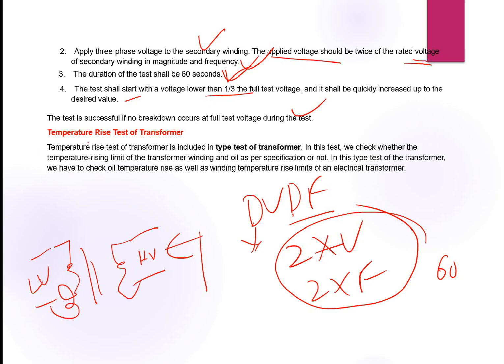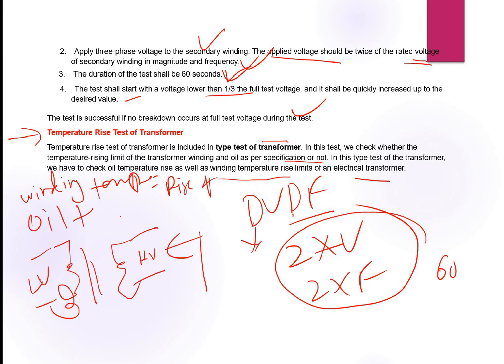Now we are going to check the temperature rise test of transformer. Temperature rise test of transformer is included in the type test of transformer. In this test, we check whether the temperature rise limit of the transformer winding and oil is as per the specified limit or not. In this type test of the transformer, we check the oil temperature rise as well as the winding temperature rise limit of the electrical transformers. We check the winding temperature rise and the oil temperature rise. It should be below the specified limit.